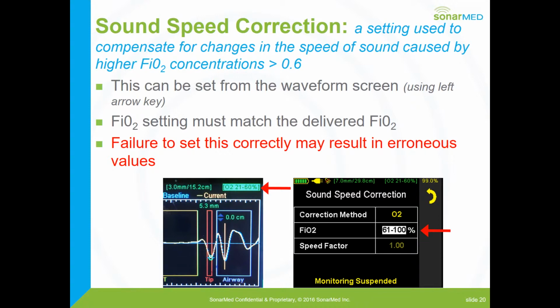Sound speed correction is a setting that you may need to use from time to time, probably not very often in the NICU, but it's going to compensate for the changes in the speed of sound caused by a higher FiO2. So if I have my oxygen set at above 60%, then I need to make a correction. I can do that in two different ways. I can do it on the waveform screen or in the settings screen.